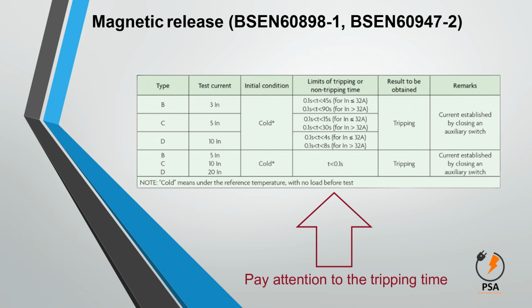B curve. In this curve, an MCB trips when the current is between 3 to 5 times the full load current. It is suitable for domestic applications where a 10A MCB will trip on 30 to 50A fault current. C curve. In this, the CB trips when the current is between 5 to 10 times the full load current. Type C MCB is suitable for commercial applications, like starting current of motors, fluorescent lights, etc.